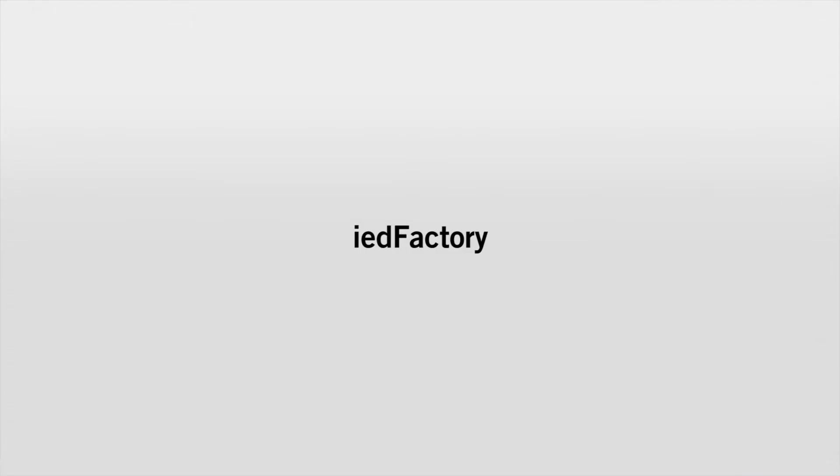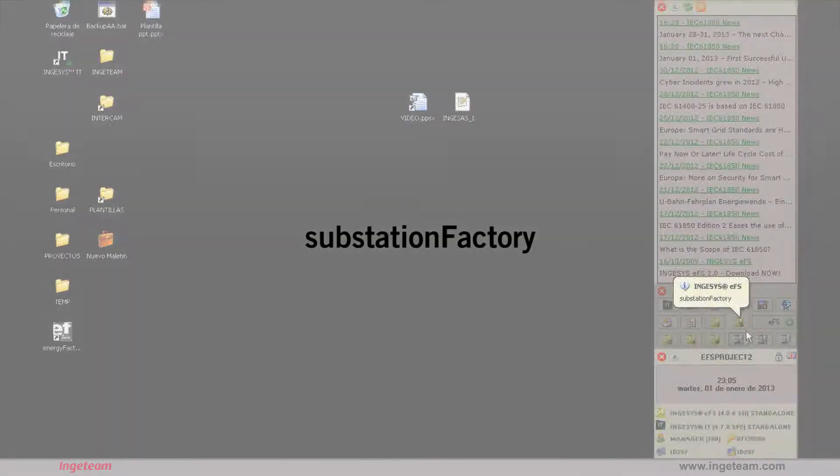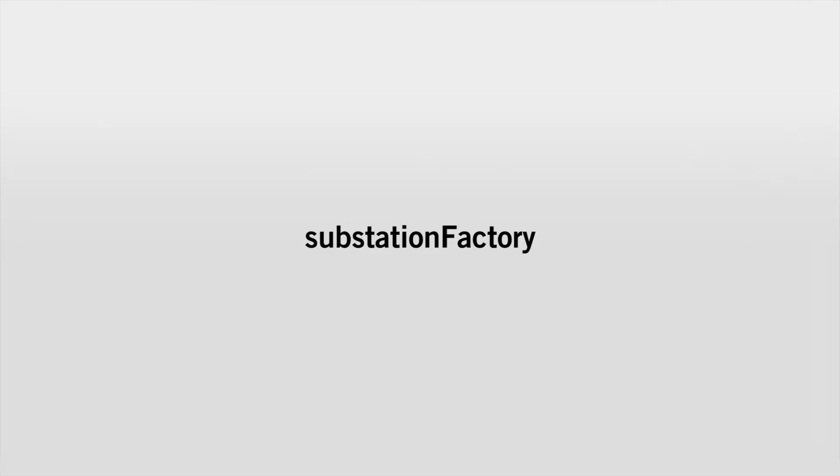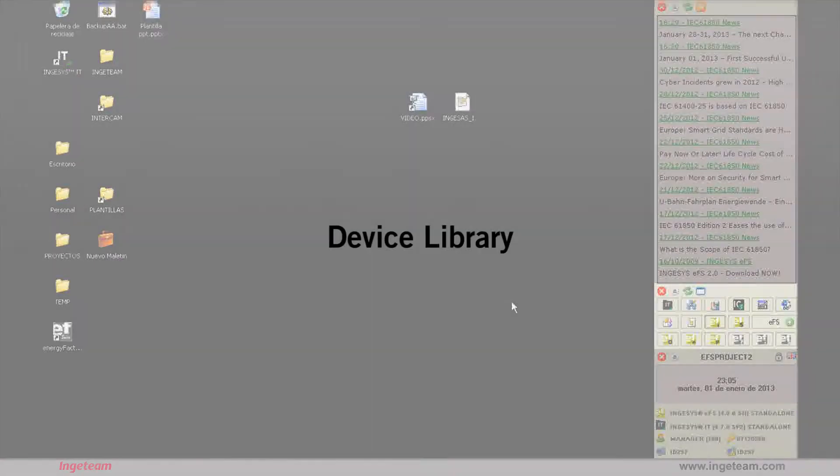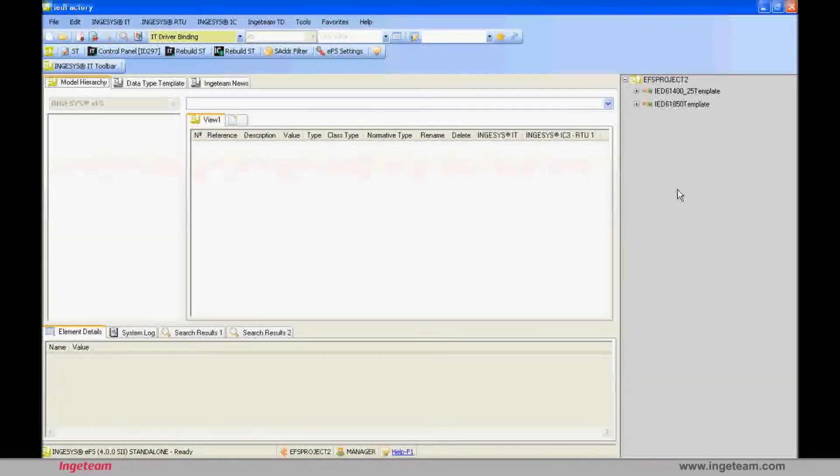Once the project has been created and activated, the two tools that we are going to work with most are IED Factory and Substation Factory. IED Factory is a tool which lets you create all of the library of the devices that you're going to use in the project. It lets you import the device models of any IEC 61850 compliant manufacturer, create IEC 61850 devices from scratch, or create devices based on other protocols. Substation Factory is the tool with which the substation is really modeled. Over the course of these videos you will see the difference between these two engineering tools.